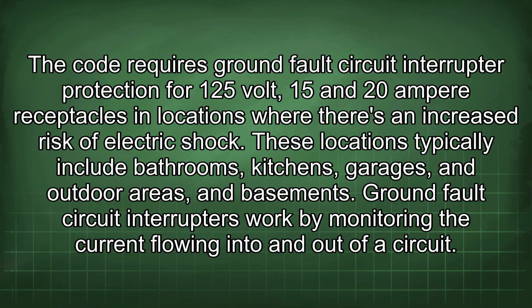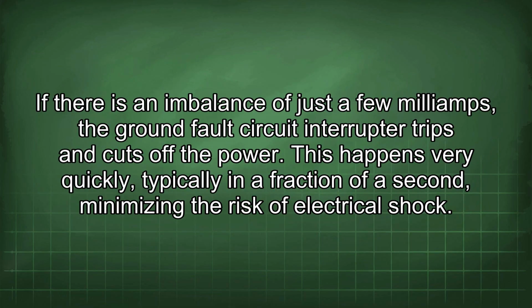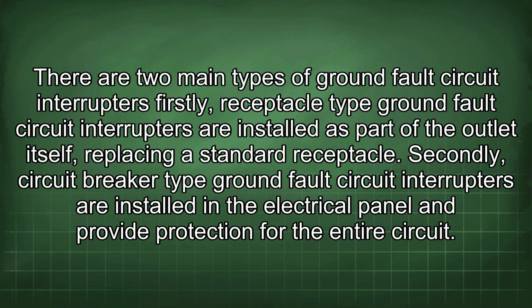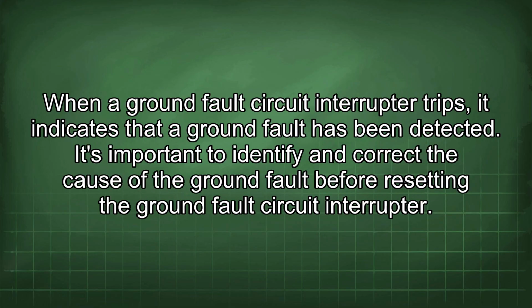Ground fault circuit interrupters work by monitoring the current flowing into and out of a circuit. If there is an imbalance of just a few milliamps, the ground fault circuit interrupter trips and cuts off the power. This happens very quickly, typically in a fraction of a second, minimizing the risk of electrical shock. There are two main types of ground fault circuit interrupters. Firstly, receptacle type ground fault circuit interrupters are installed as part of the outlet itself, replacing a standard receptacle. Secondly, circuit breaker type ground fault circuit interrupters are installed in the electrical panel and provide protection for the entire circuit.